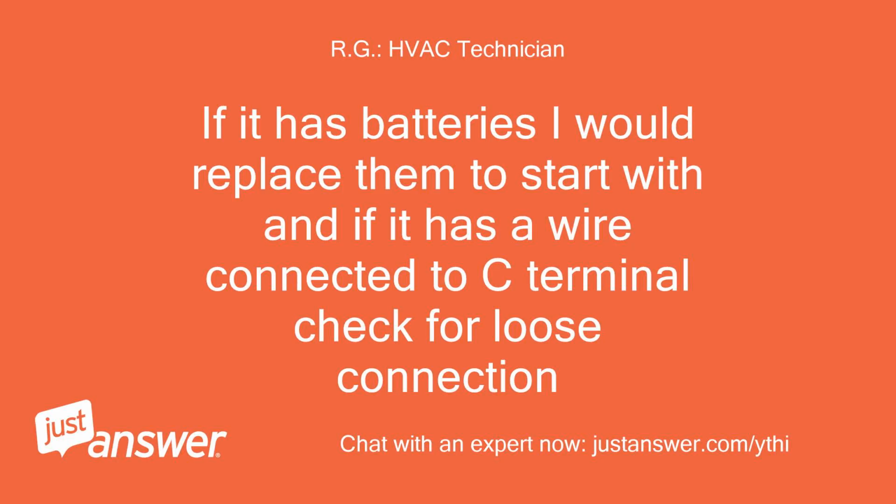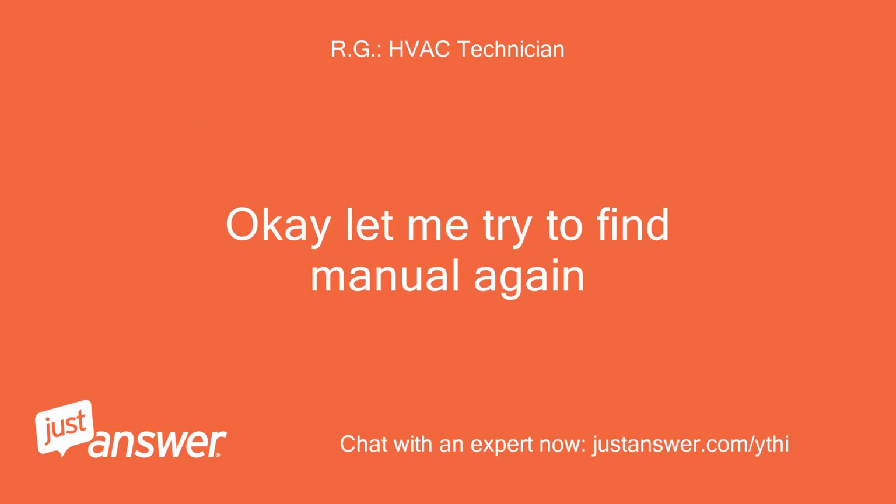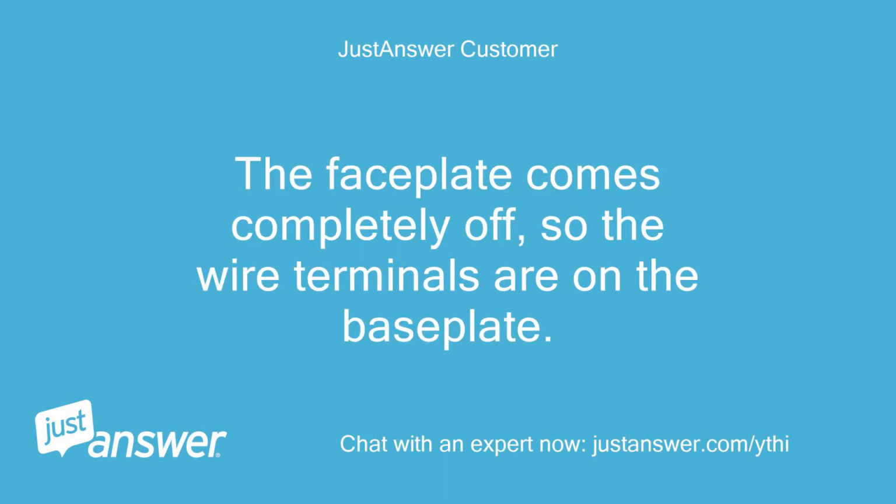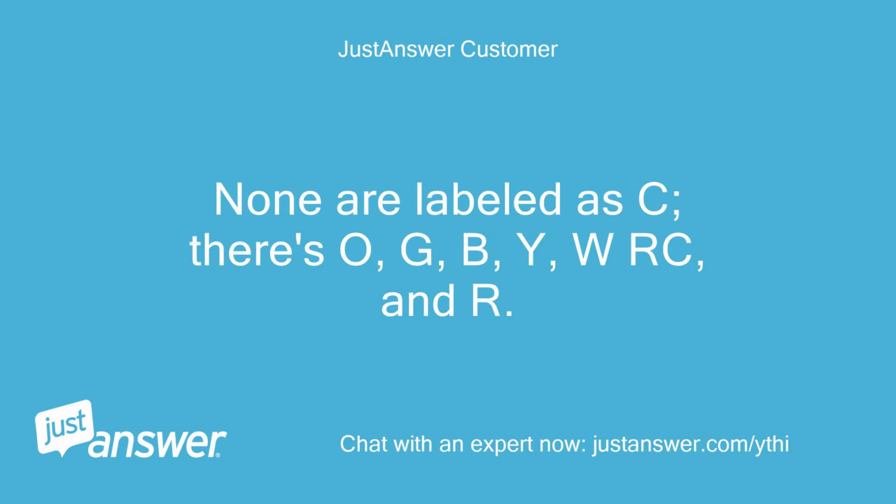If it has batteries, I would replace them to start with, and if it has a wire connected to the C terminal, check for loose connection. Okay, let me try to find manual again. And no batteries. The faceplate comes completely off, so the wire terminals are on the base plate. None are labeled as C, there's an O, G, B, Y, W, RC, and R.